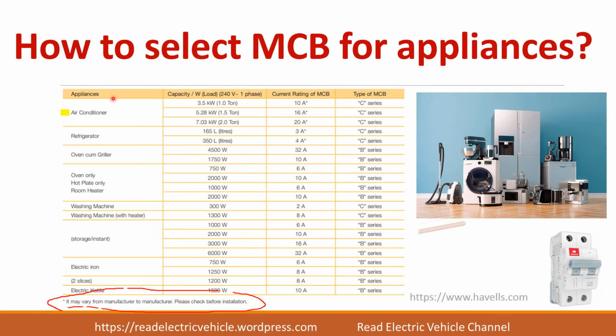If you take an air conditioner, depending upon the capacity of it, you can choose the current rating, and preferably they are using C type MCB. And for a refrigerator also they are using C type, but the amp requirement, the current requirement, is less. So similarly for each appliance you can choose the current rating of the MCB depending upon the power rating of your device.